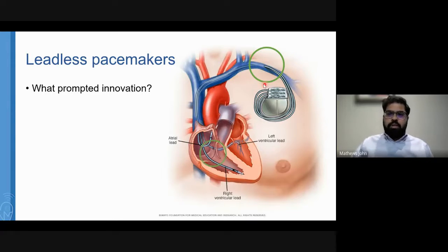The other problem is, if you look here, there's a valve between the right atrium and the right ventricle. If you have a wire sticking through the valve, it may not close, even in a relatively healthy patient. And that can cause what's called tricuspid regurgitation, where the blood flows back from the ventricle into the atrium. That's not supposed to happen. And over time, the valve's mechanical function can actually deteriorate. The last bit is lead dislodgement, where the leads can actually come out or fracture because of all the continuous mechanical movement across 5 to 10 years.